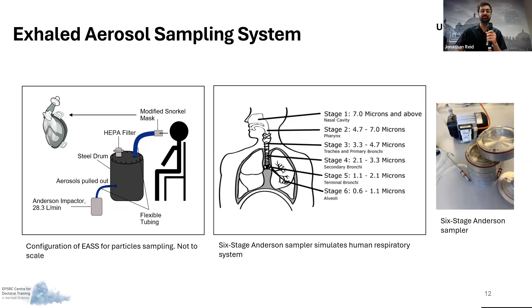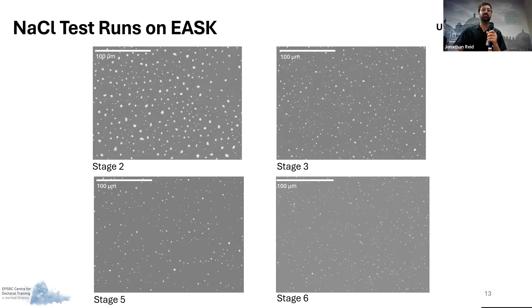For example, we have been using SEM stubs in these experiments. You can use polycarbonate filters and TEM stubs as well in this system. So we ran some test runs with this equipment with sodium chloride to see whether our system is working or not. We could see good distribution of particles. These particles are directly collected on SEM stubs, and we could get a good distribution on different stages of the system. It seems like the system is working, so that's good.